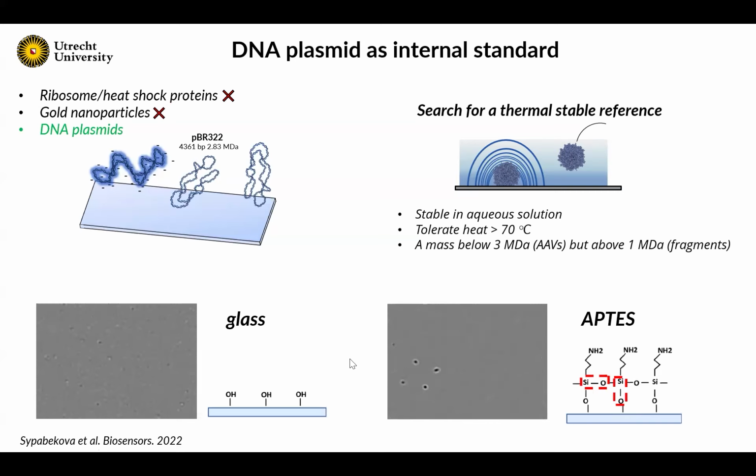However, what you might also see is that some of these signals have a bit of a strange oval-like shape, which we did not see earlier, which is different from the circular shapes we are used to with our mass photometry measurements. So here we have a frame with a zoom, and you can clearly see these strange oval shapes, which are different from the circular landing events that we are used to seeing. And this would be because the DNA plasmid is quite big, it has quite a long length, and it now starts to become close to the diffraction limit of the mass photometer.